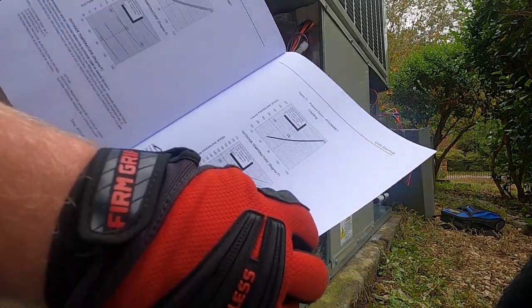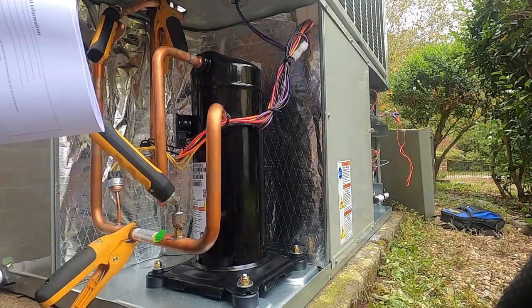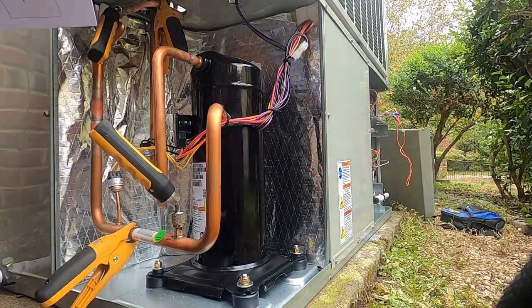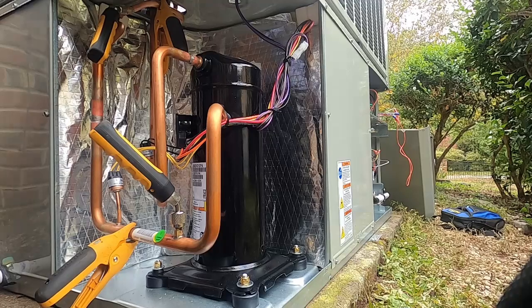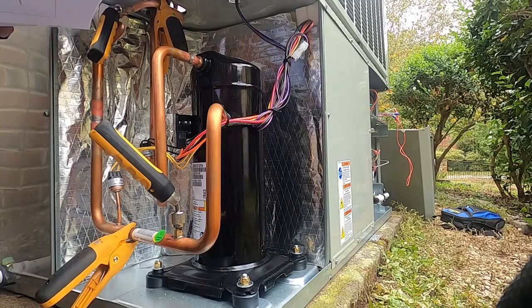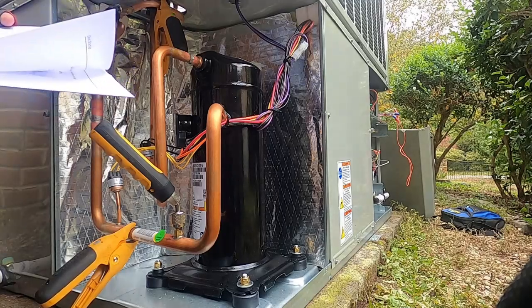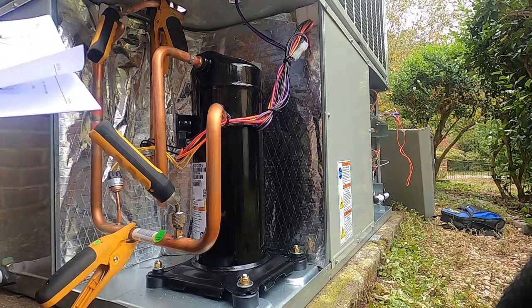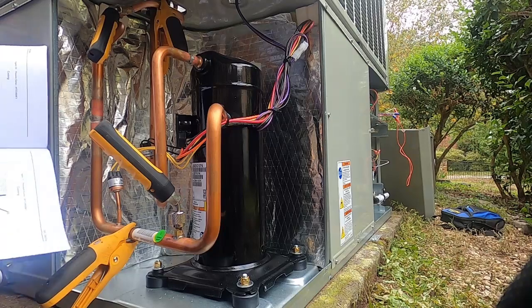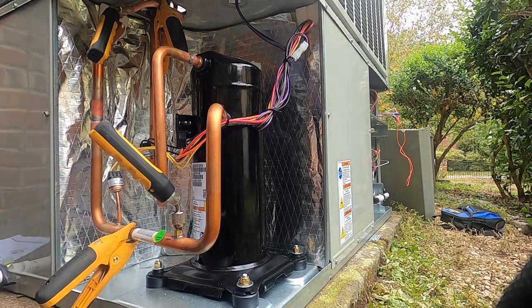So not quite sure where we're going to be on our target subcooling. Let me see if it says anything down there. Discharge, suction. This is a 3 or 2.5 ton. Find the intersection. It just tells you how to use the chart on it. I don't see anything on here unless it's in some small obscure print somewhere. I don't see anything that has anything about subcooling. So we've got the pressure curves. I'm going to be under the assumption that this is a brand new system and we are going to be good.